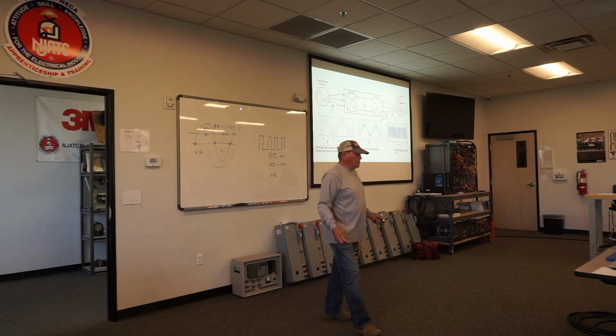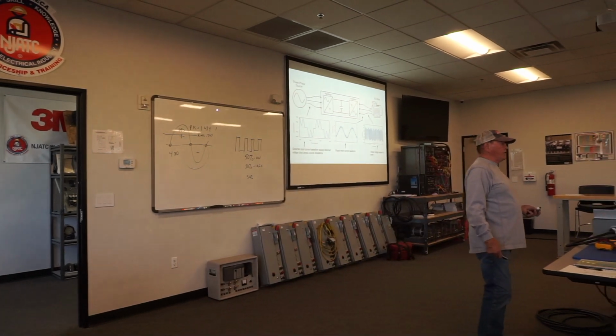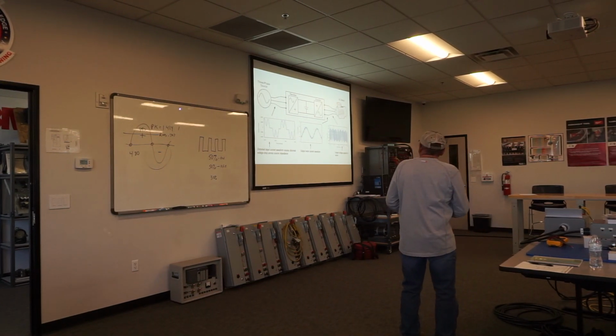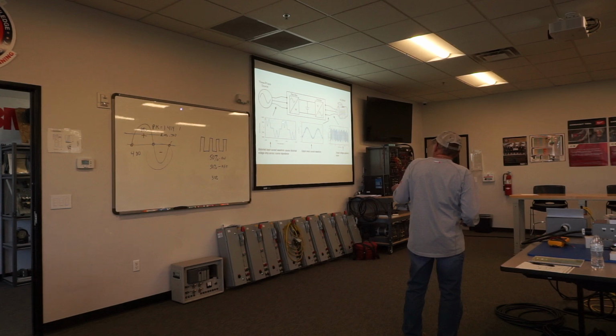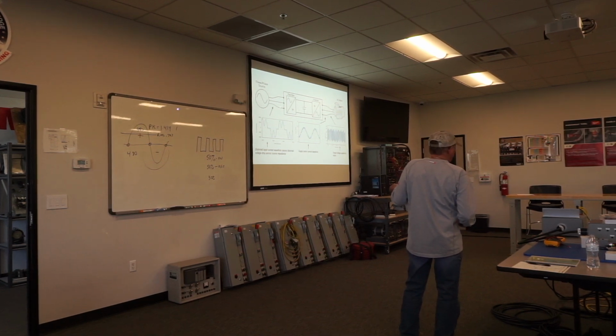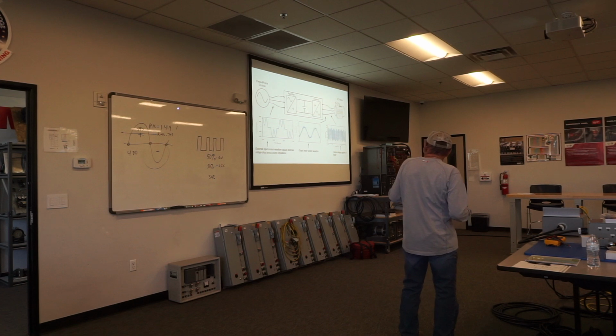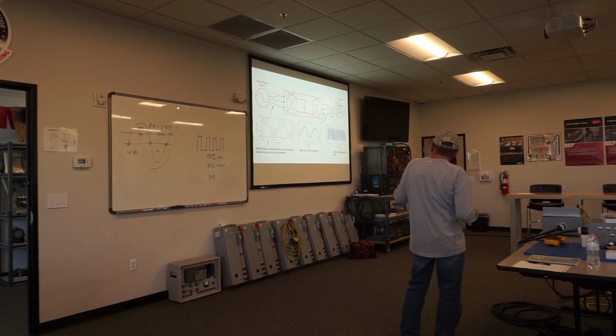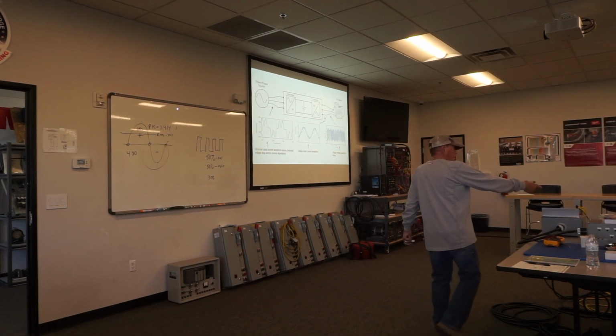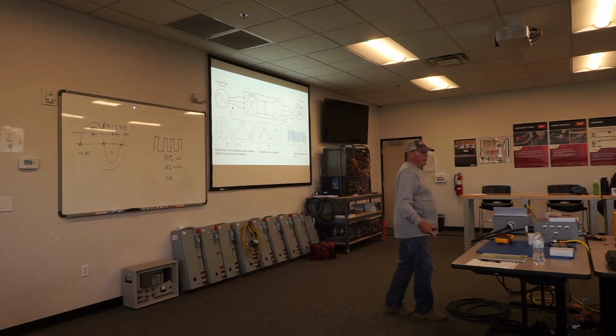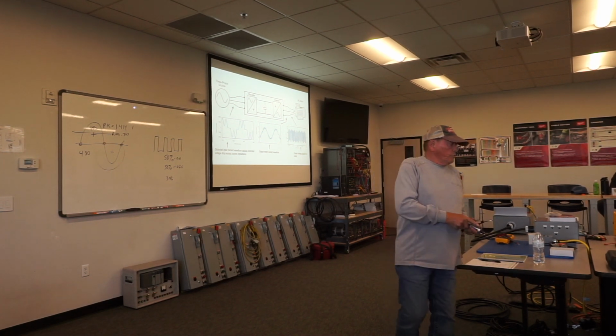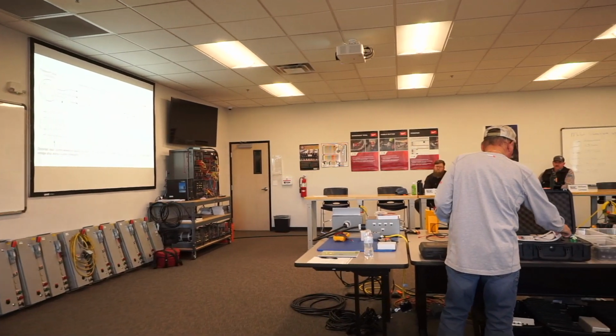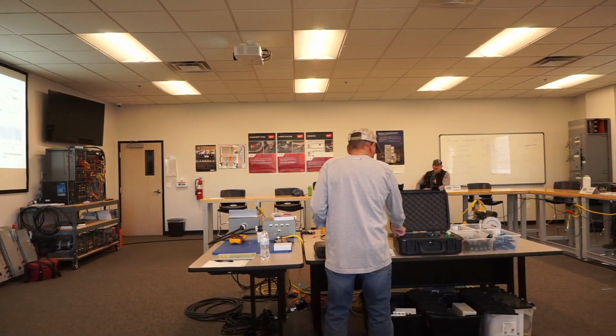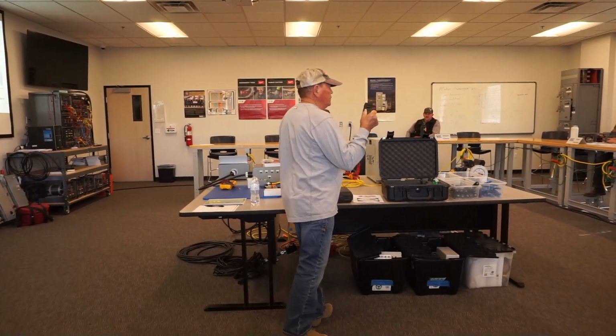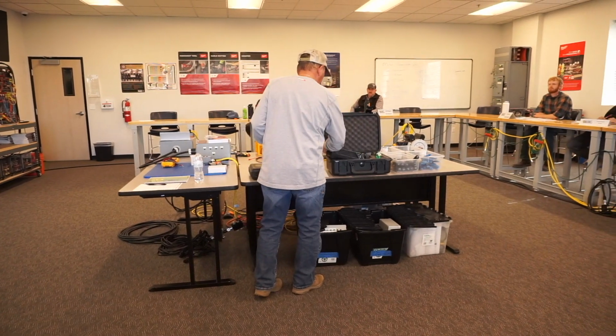So with proper test equipment, most multimeters can measure DC volts as well as AC. So I can check the voltage of my input to find out where my problem is coming from. I can check my DC bus for the most part, just have to open up the drive and check for DC voltage. Here on this side, I need a scope, like we have sitting here. And using a scope, when you get into some real fine test requirements, this is my portable scope that I use for testing motors.